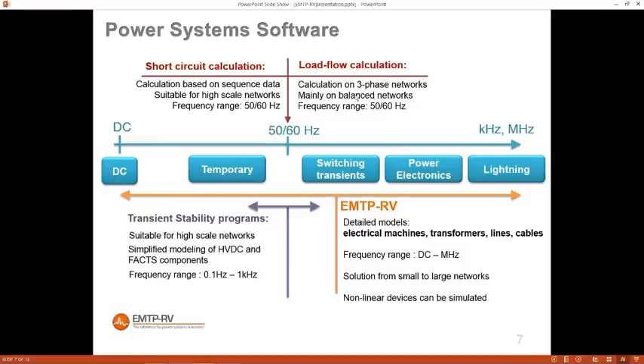These models also reproduce the propagation of waveforms through the line. For example, with a 200 km line, if you energize one end, nothing happens at the other end initially — a waveform travels through the line, reflects at the far end, and comes back, creating back-and-forth reflections that are eventually damped by the resistance. This behavior has a big influence on overvoltage. We can also simulate slower phenomena like temporary overvoltages, and DC phenomena for HVDC or wind turbines.